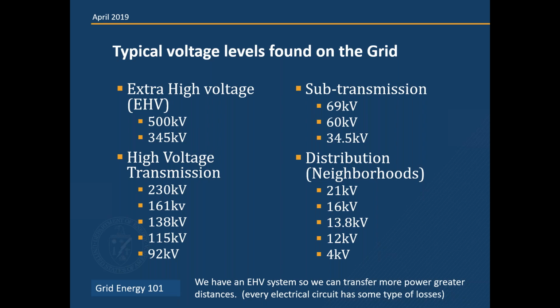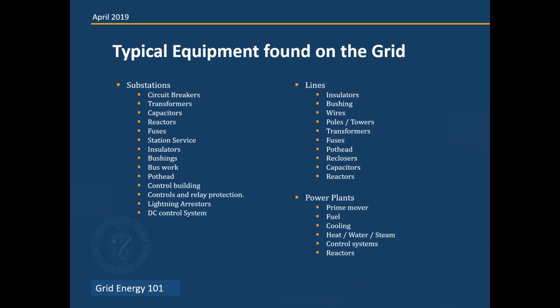And then we have just your high voltage transmission system. 230 kV, 161, 138, 115, 92 kV. And again, this is not all inclusive. There's some other oddball voltages you might see out there. Then you have a sub-transmission system, which is 69 kV, 60 kV, 34.5 kV. And then we kind of get down into the neighborhoods, 21 kV, 16 kV, 13 kV, 12, and 4 kV. Again, this is not an all-inclusive list. Next slide, please.